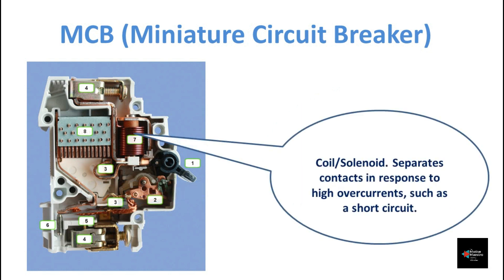The solenoid coil: when a very high current is passed through the MCB, the magnetic tripping coil will be magnetized and it will trigger the actuator latch mechanism. This trigger will cause the contacts to separate.